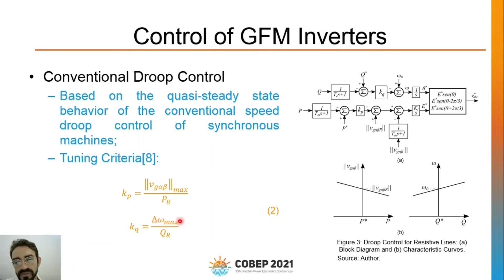And the tuning criteria is based on the steady-state operation points of the inverter. The tuning is defined as the ratio between the maximum deviation at steady state for voltage and the rated active power, or the gain related to active power droop. And for the gain in the reactive power droop, we have the maximum frequency deviation over the rated reactive power.